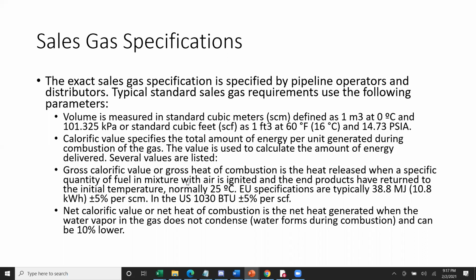Gross calorific value, or gross heat of combustion, is the heat released when a specific quantity of fuel in the mixture with air is ignited and the end products have returned to the initial temperature, normally at 25 degrees Celsius. EU specifications are typically 38.8 megajoules or 10.8 kilowatt hours, plus or minus 5% per standard cubic meter. In the US, it's 1030 BTU, plus or minus 5% per standard cubic foot. Net calorific value, or net heat of combustion, is the net heat generated when the water vapor in the gas does not condense, so water forms during combustion, and can be 10% lower.